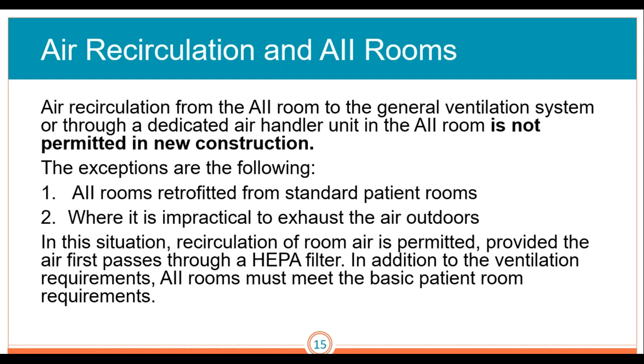Air recirculation in AII rooms: air recirculation from the AII room to the general ventilation system or through a dedicated air handler unit in the AII room is not permitted in new construction. We have some exceptions: one, AII rooms that are retrofitted from a standard patient room; and two, where it is impractical to exhaust the air outdoors. In this situation, recirculation of room air is permitted provided the air first passes through a HEPA filter in addition to the ventilation requirements. AII rooms must meet the basic patient room requirements.